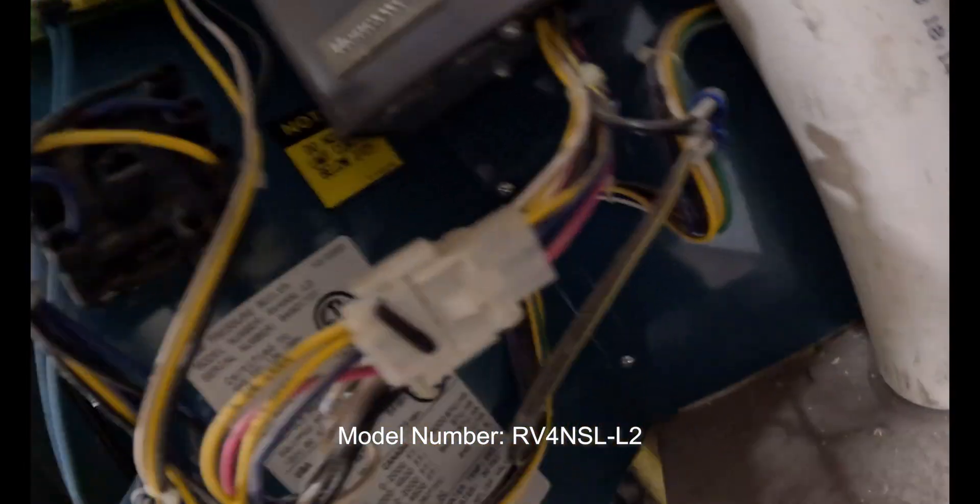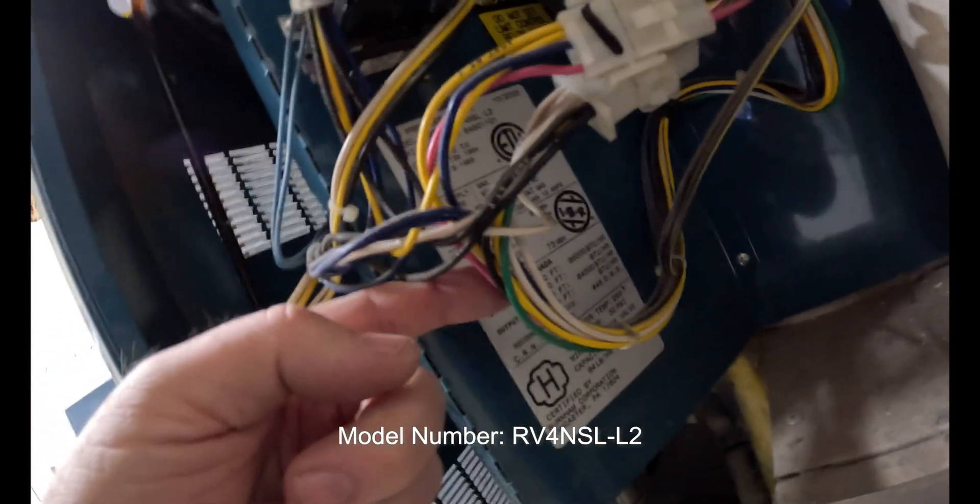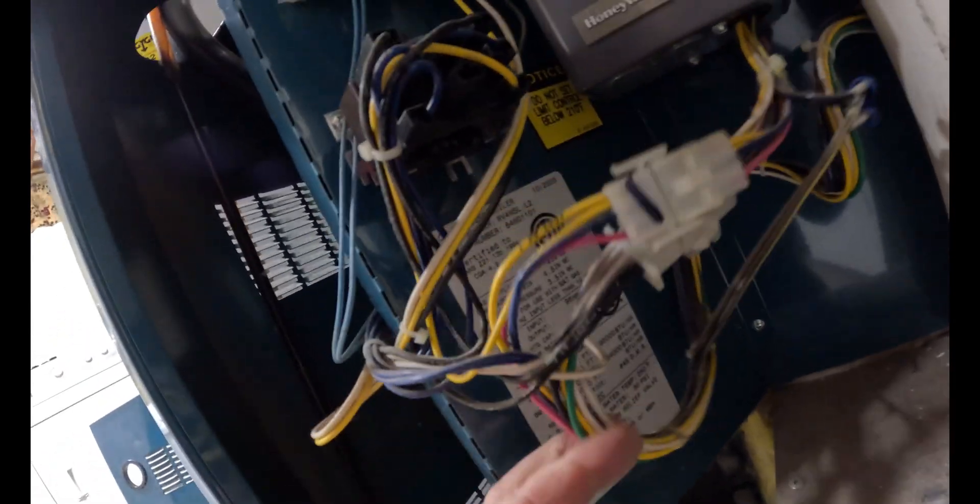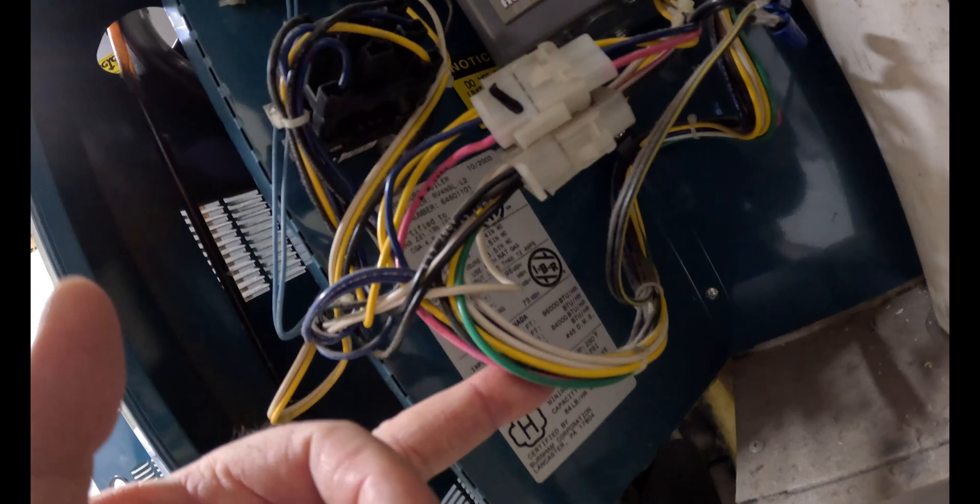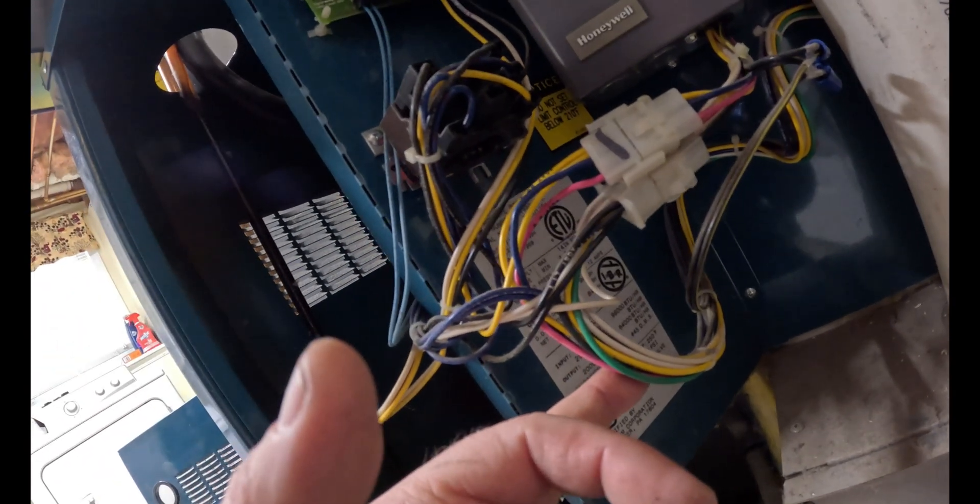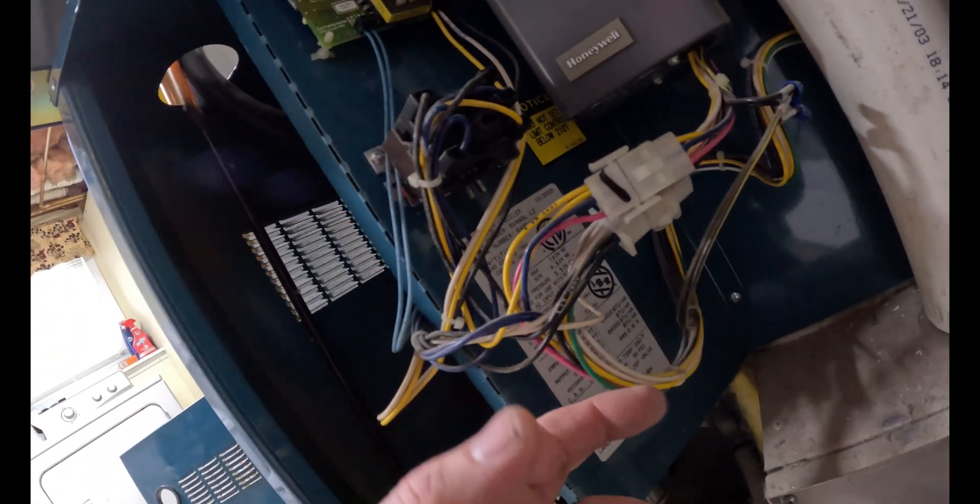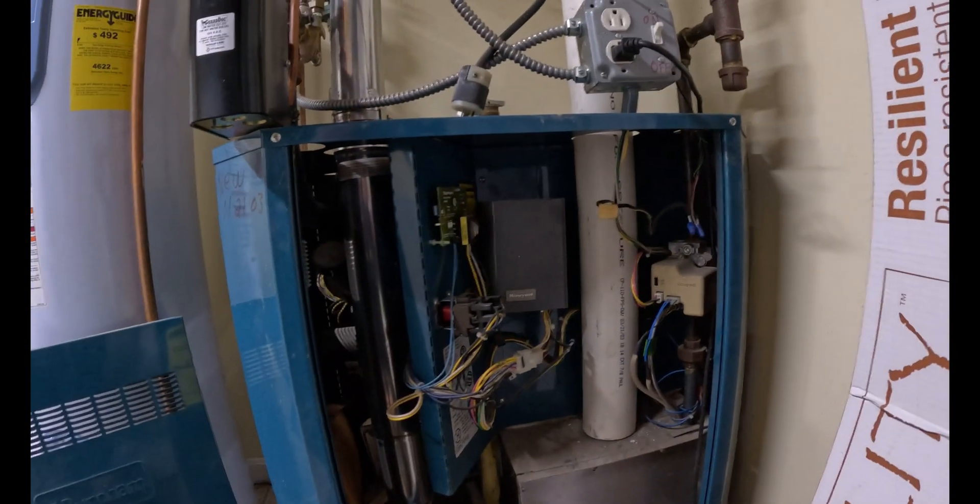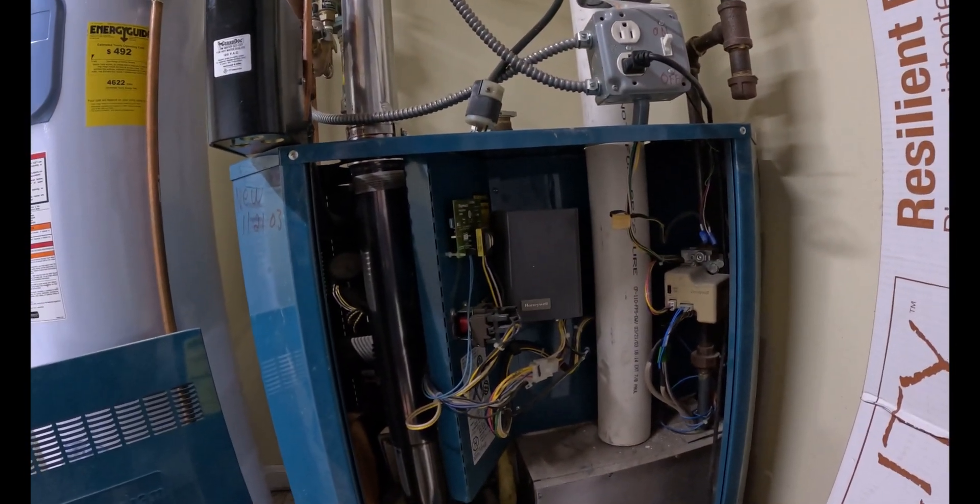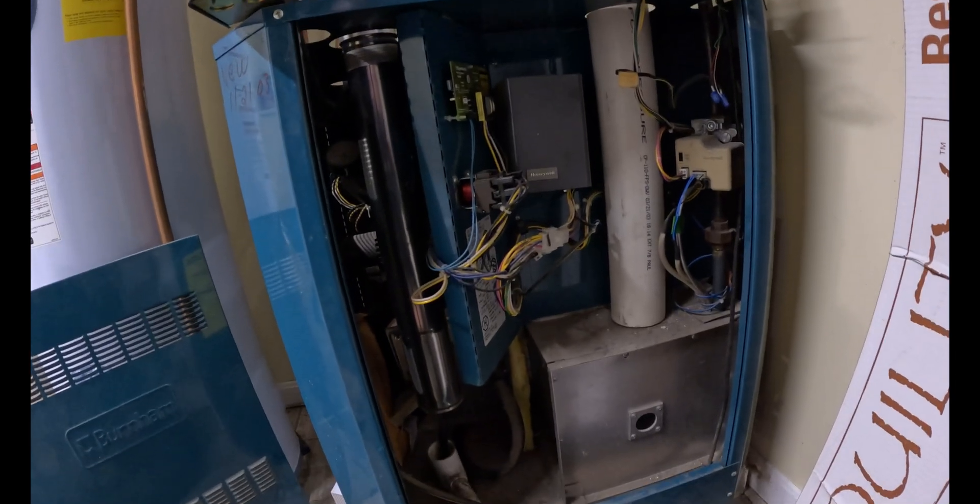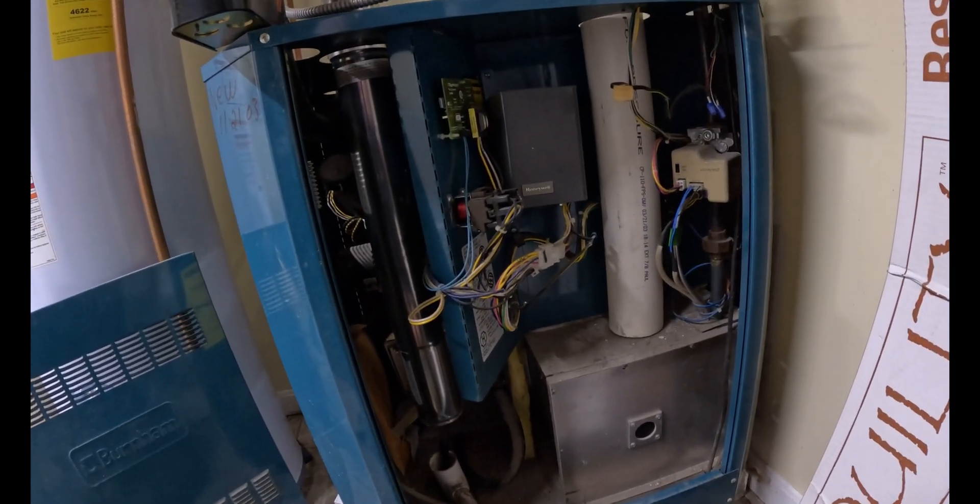Again, this is a Burnham Revolution boiler. This boiler here, input is 96,000 BTU, which is kind of big for this house. You're going to get 84,000 out. So nice boiler for, you know, pretty standard home, 2,000 square foot home kind of thing, plenty big for that. You could put an indirect on this thing if you want to.